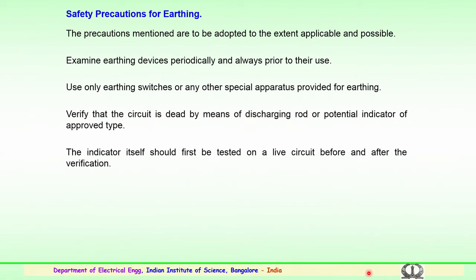An important aspect of the precautions is the earthing or grounding, which we have tried to discuss. The precautions mentioned are to be adopted to the extent applicable and possible. Even though the substation is grounded and the equipment is grounded, the safety precaution of earthing or grounding is very important. So, personnel should examine the earthing devices periodically and always prior to their use, and they have to use only earthing switches or any other special apparatus provided for earthing.